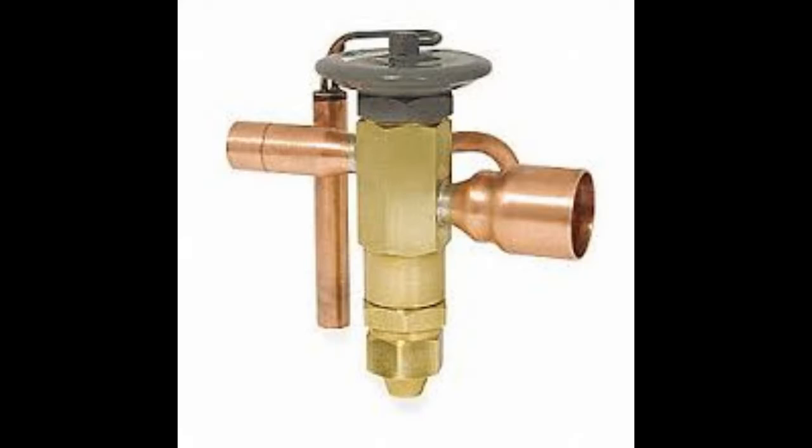So what comes next is the thermostatic expansion valve. So we move on to the thermostatic expansion valve. Don't let the name fool you. This mushroom-shaped valve has a very simple job. And although it's one of the smallest components of the air conditioning system, it has one of the biggest jobs. It acts as a restrictive point in the refrigerant cycle so that the refrigerant enters the evaporator coil as a low-pressure liquid. In essence, it keeps the refrigerant cycle running efficiently.